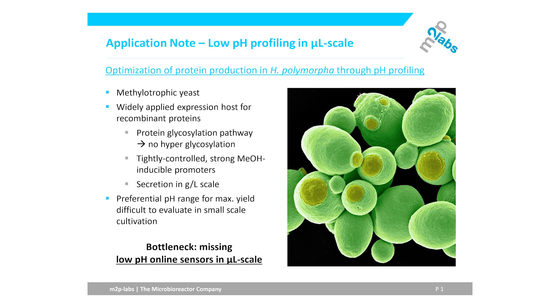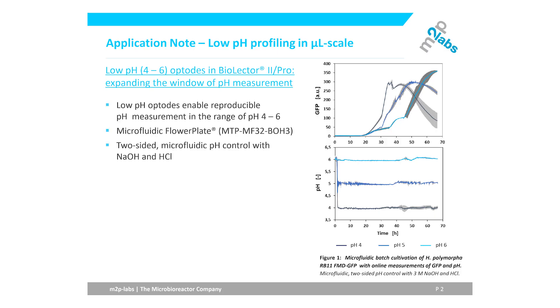Thus, some kind of a bottleneck evolved with respect to missing low pH online sensors in MTP-based microliter scale. However, in this application note, we demonstrate the use of a new low pH optode in BioLector Pro that expands the measurement window to a lower range of 4 to 6.